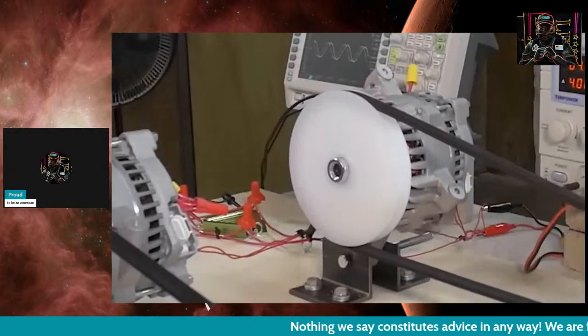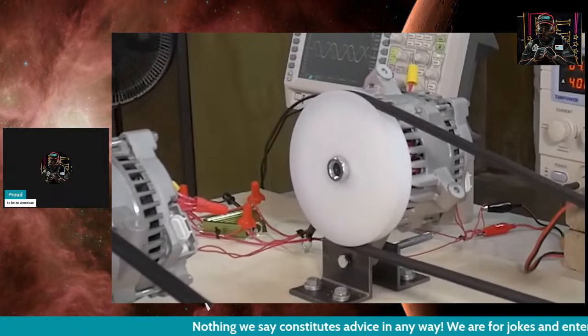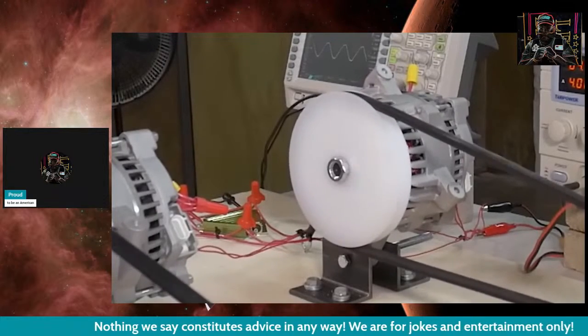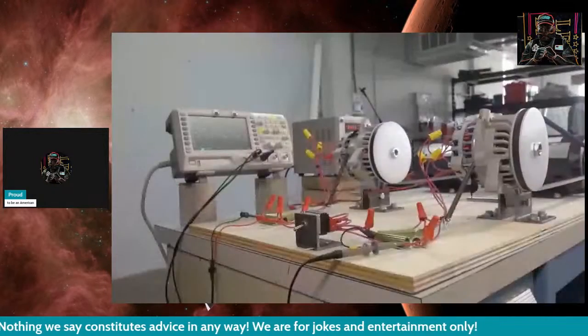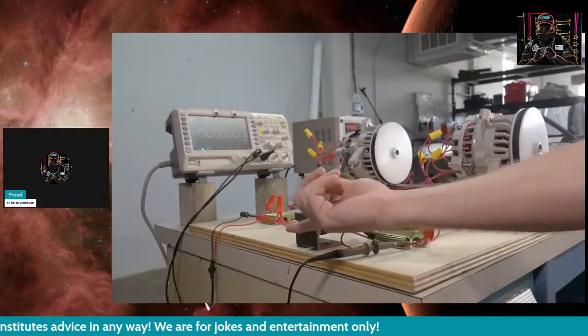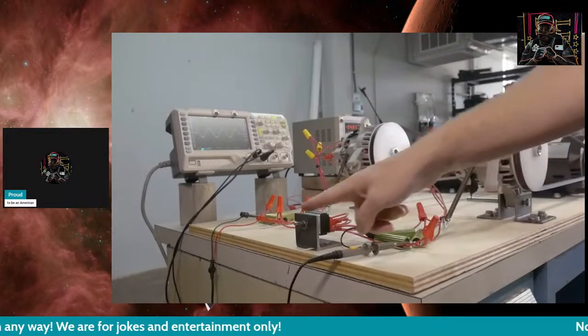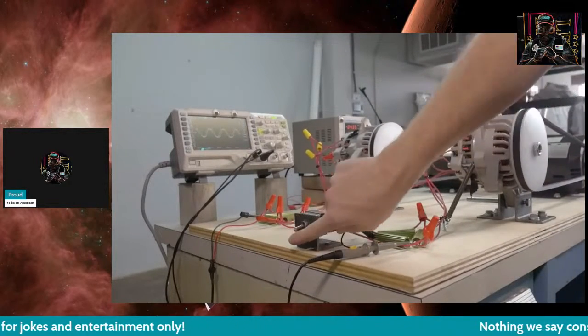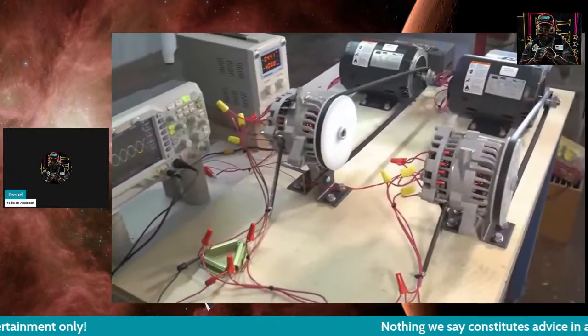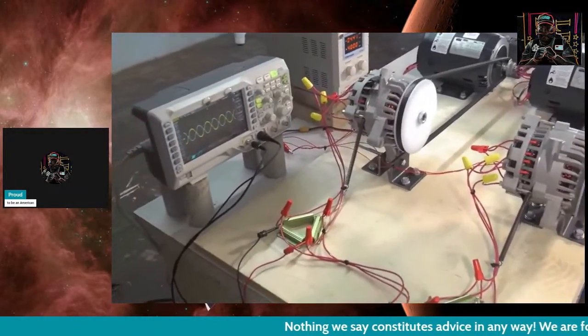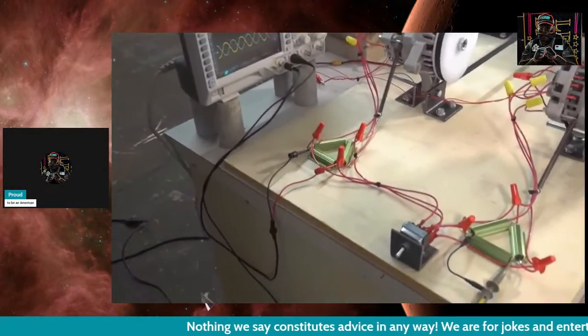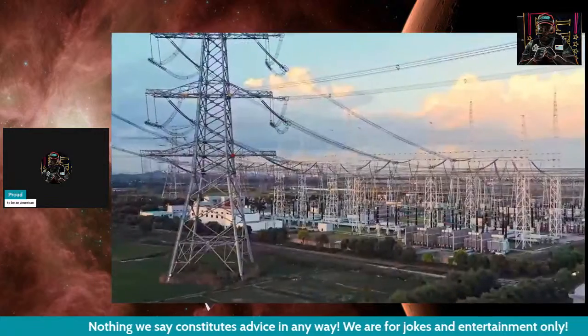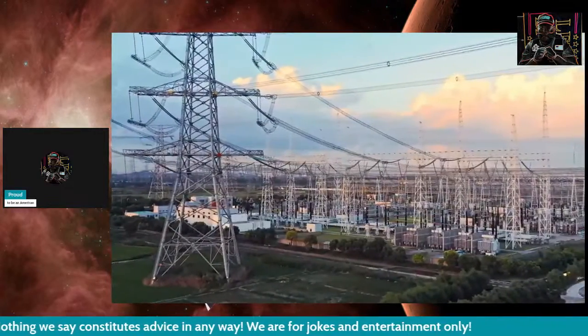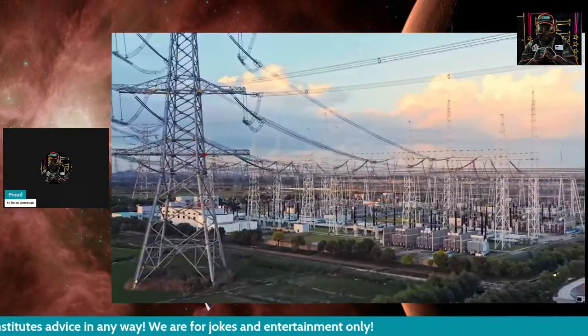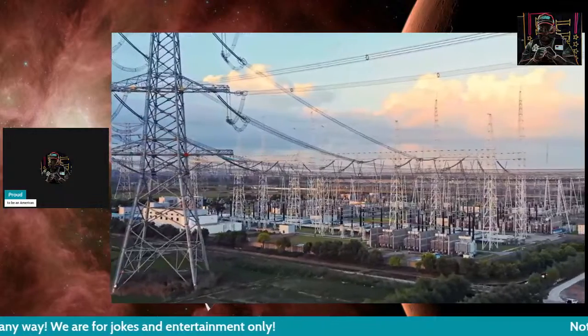If I flip the switch when the two generators are out of sync, they jerk as the magnetic fields equalize their current. If the difference is big enough, the two generators actually fight against each other, essentially trying to drive each other like motors. It's kind of fun with this little model, but something like this in a real power plant would cause tremendous damage to equipment. So during a black start, each island, and in fact each individual power plant that comes online, has to be perfectly synchronized.